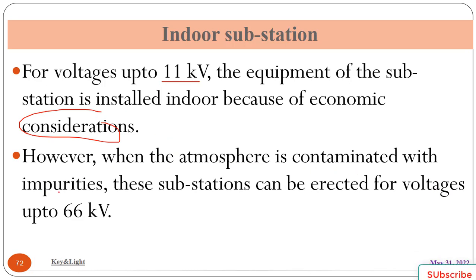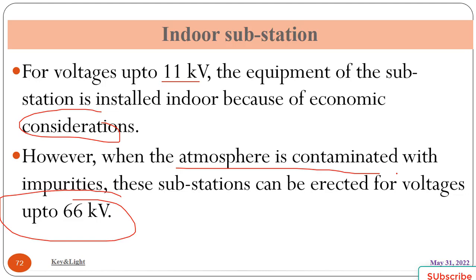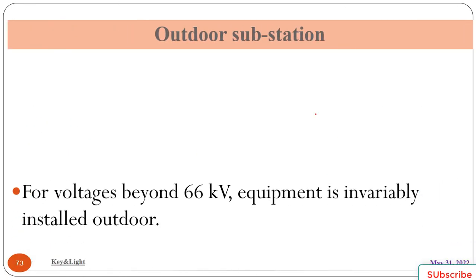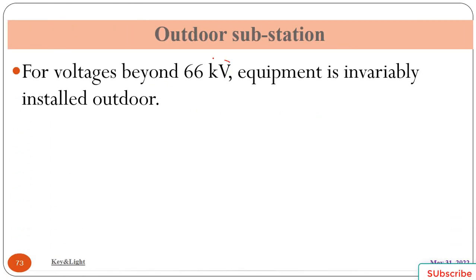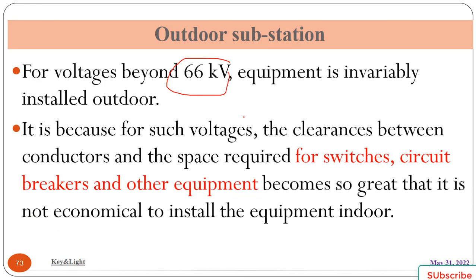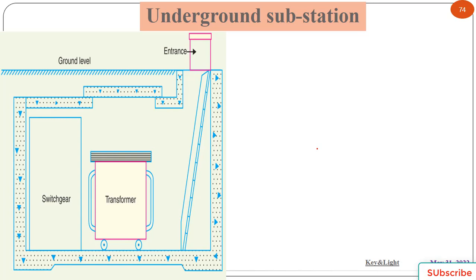However, where the atmosphere is contaminated with impurities, these substations can be erected for a voltage of 66 kV if the atmosphere is contaminated. The next one is the outdoor substation. For a voltage beyond 66 kV, equipment is invariably installed outdoor. It is because for such voltage, the clearance between conductors and the space required for switches, circuit breakers, and other equipment become so great that it is not economical to install the equipment indoor.